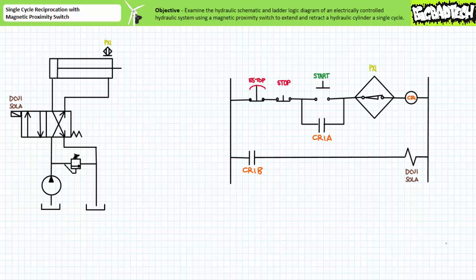The one exception being the diamond symbol surrounding it. This symbol represents a solid state magnetic proximity switch PX1. Magnetic proximity switches are used to detect the presence or absence of a magnetic object inside the range of a magnetic field produced by the switch without the necessity of having to make physical contact with the object.